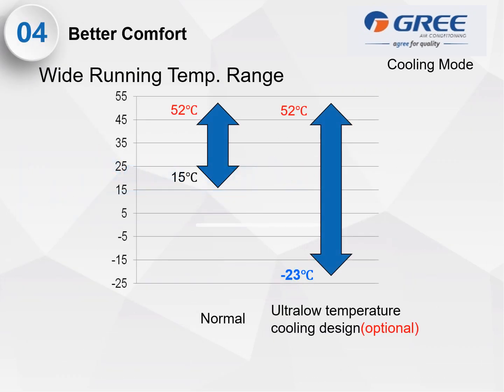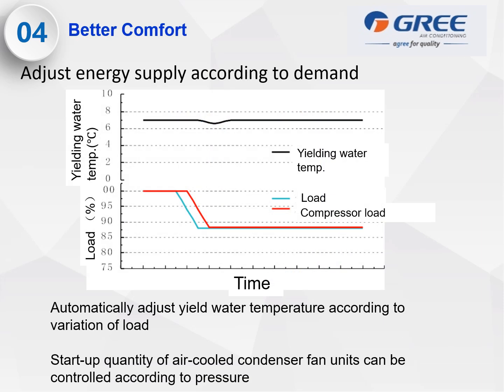For better comfort, it has a wide running temperature range. It can go on ultra low temperature cooling design. This is optional, meaning you can add glycol in the system if you need to operate at minus 23 degrees C. It adjusts energy supply according to demand, because it automatically adjusts outlet water temperature according to variation of load. Remember, this is a screw chiller, meaning you can drop the demand down to 12.5%. Startup quantity of air-cooled condenser fan units can be controlled according to pressure.